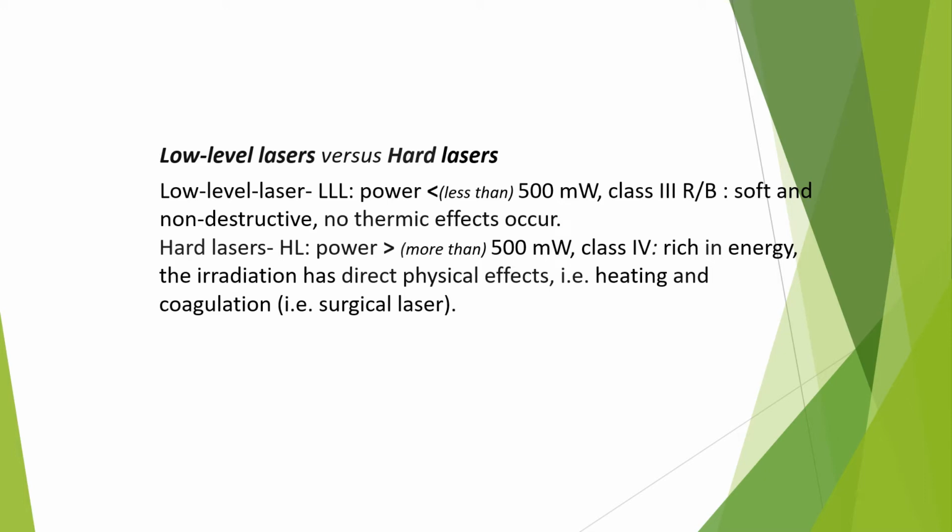Low-level lasers versus hard lasers. Low-level lasers have power less than 500 milliwatts. They are class 3R or B, soft and not destructive. No thermic effects occur when they are applied.